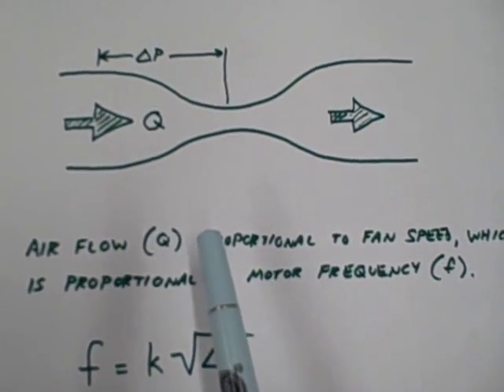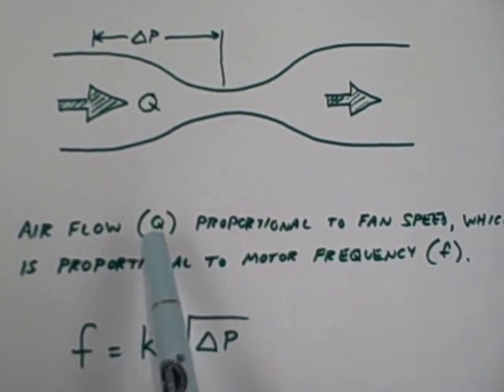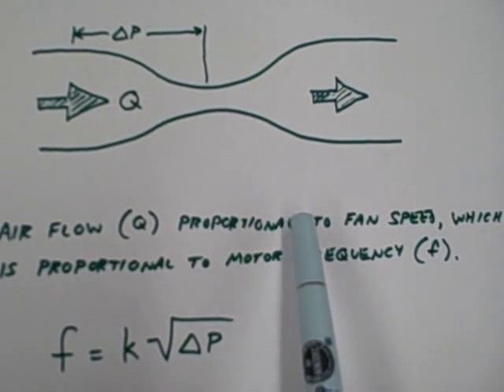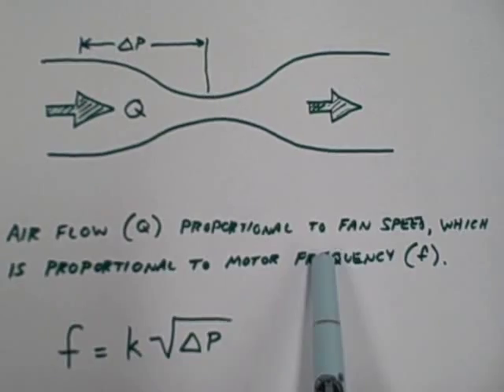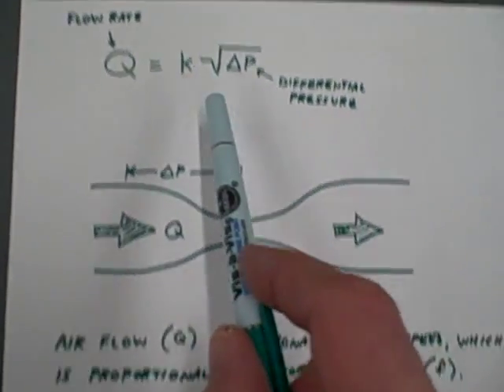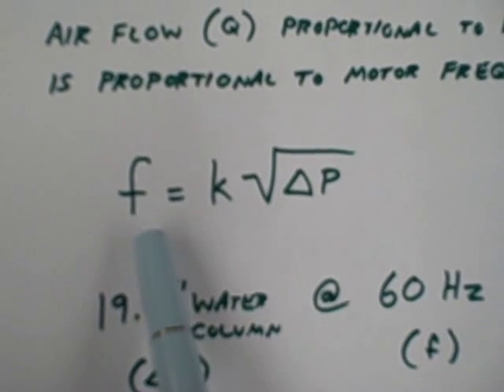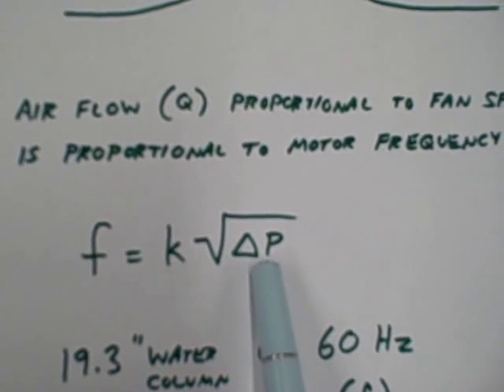In this case, we know the air is being driven by a variable speed fan, and the nature of the fan's operation is that air flow rate will be proportional to the speed the fan turns, which in this case is proportional to the frequency we're driving the motor at. So we can rewrite our proportionality as this: the frequency we're driving the motor is equal to some constant proportionality times the square root of differential pressure.